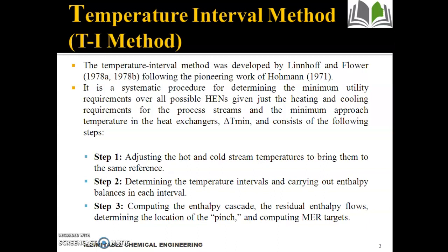Temperature interval method. The temperature interval method was developed by Linnhoff and Flower following the pioneering work of Hohmann in 1971. It is a systematic procedure for determining the minimum utility requirements over all possible heat exchanger networks, given just the heating and cooling requirements for the process streams and the minimum approach temperature in the heat exchanger, that is delta T minimum, and consists of the following steps.